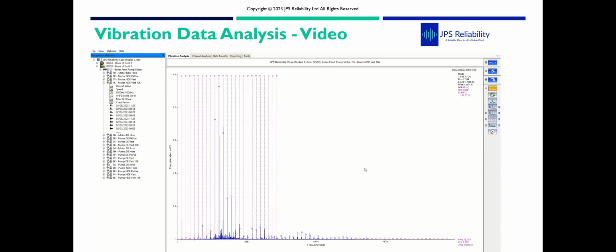But what's different about this, which shows you it's EDM, is you usually get this high amount of activity, sometimes around the drive frequency, and it's sidebanded by outer race, whereas with a normal outer race defect frequency, you usually get a higher one order BPFO, 2, and it sort of comes down like it's ringing. This is the bearing basically screaming because of the drive.